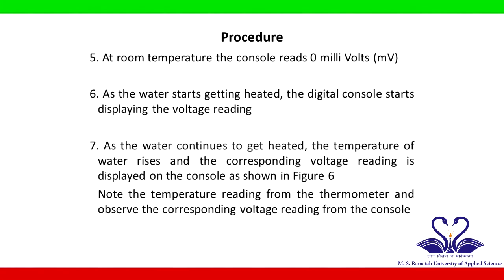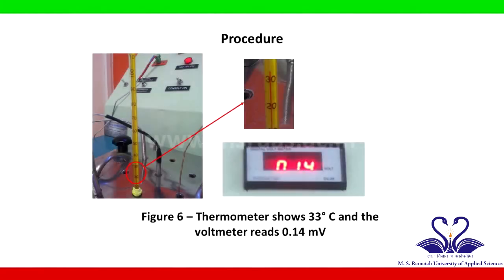At room temperature, the console is set such that it reads 0 millivolt. As the water starts getting heated, the digital console starts displaying a voltage reading. As the water continues to heat, its temperature rises gradually and the voltage generated at that corresponding temperature is displayed on the console. Note down the temperature reading from the thermometer and observe the corresponding voltage reading from the console. For example, in figure 6, we can see that at a temperature of 33 degrees Celsius, the voltmeter reads 0.14 millivolts.